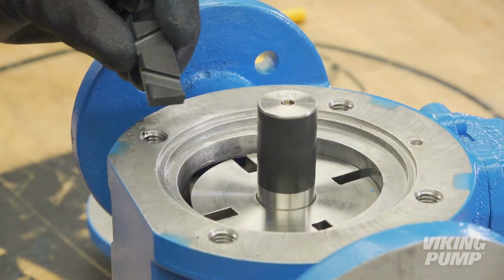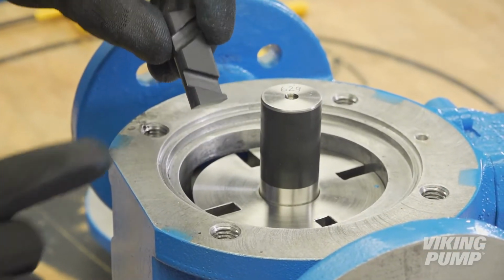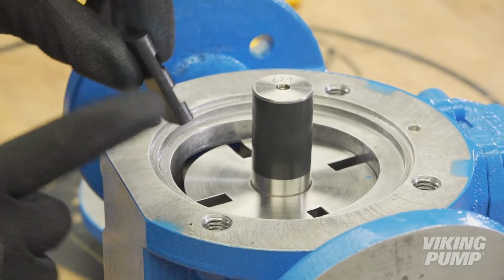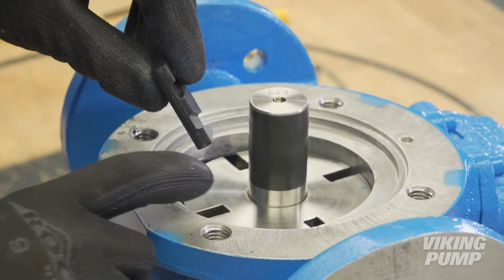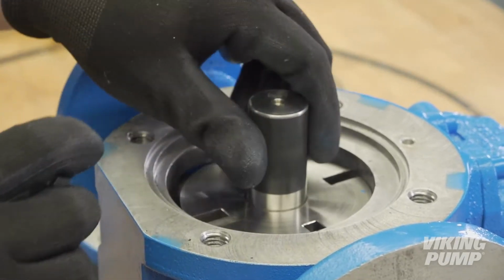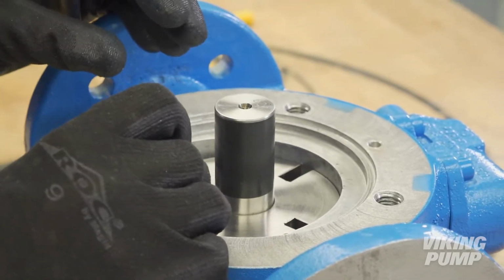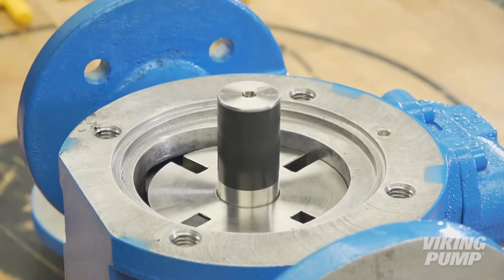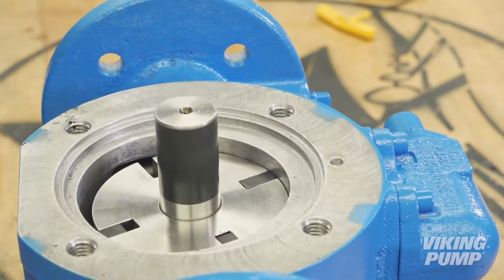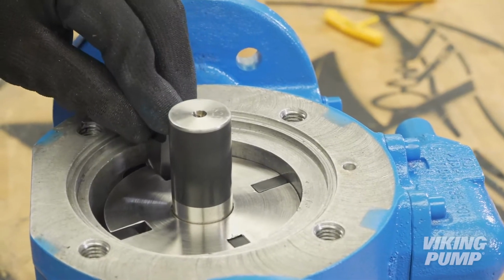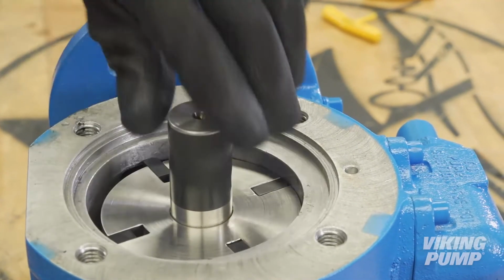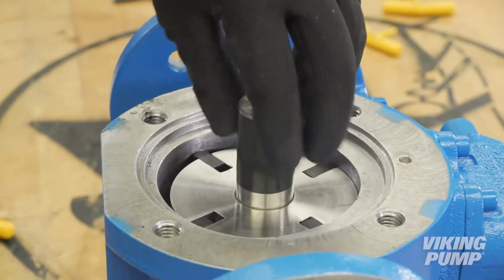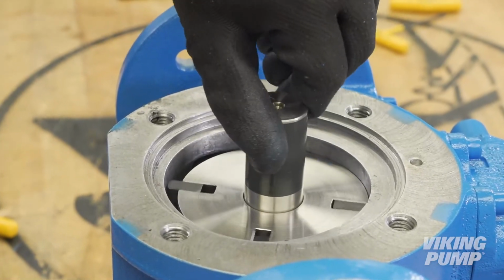Install the vanes into each slot. Orientation is critical for proper pump operation. Ensure the grooved face of each vane is facing in the direction of rotation and that the rounded edge points out from the shaft. Turning the shaft by hand should allow the push rods to slide down, allowing vanes to be installed. Turn the shaft to make sure the vanes and push rods are moving freely.